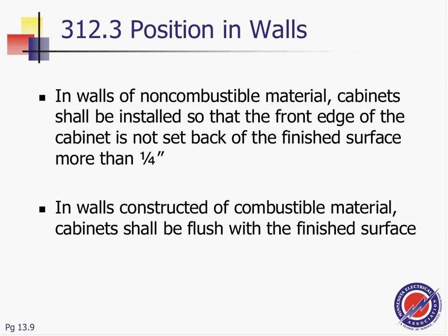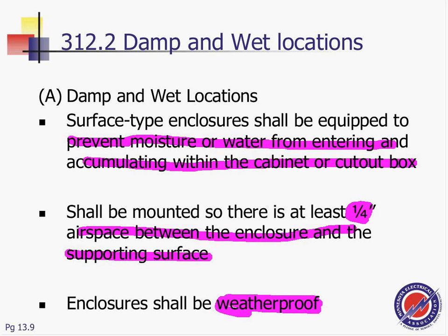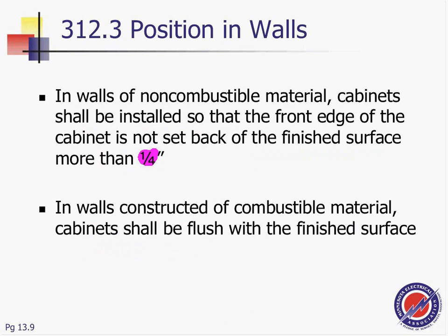Position in the wall, very interesting. So we know if it's outside, guys, how they have to be mounted. Again, I can't emphasize where we are. We're in a damp or wet location. We're not in a dry location, so that's what you're going to mean by damp and wet location. A basement is a good example of a damp location.